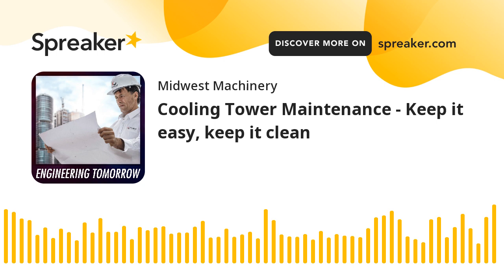There's going to be multiple places where you can check the oil, depending upon your cooling tower and how it's configured. But just like any other piece of machinery, you have to make sure that oil looks good. Marley would recommend that you change the oil every 5 years. Okay, and Marley, Midwest Machinery, we rep Marley Cooling Towers here. They recommend checking the oil every 5 years. And that's just for a Marley-specific gearbox. You need to consult if you're using a different type of gearbox. Different manufacturer, yep, okay. Yes.